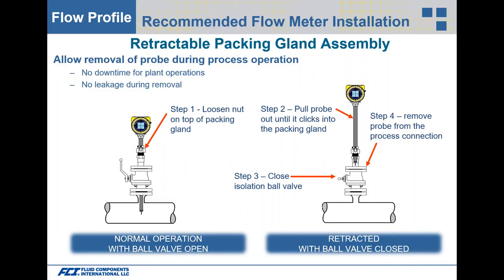For installation best practices, if you don't want to shut down the gas process to remove the flow meter, use a ball valve with a packing gland assembly on the flow element. To extract without shutdown: loosen the top nut on the packing gland, extract the flow element up into the packing gland where it clicks in, close the isolation ball valve, then remove the probe from the process connection — without ever shutting down the process.